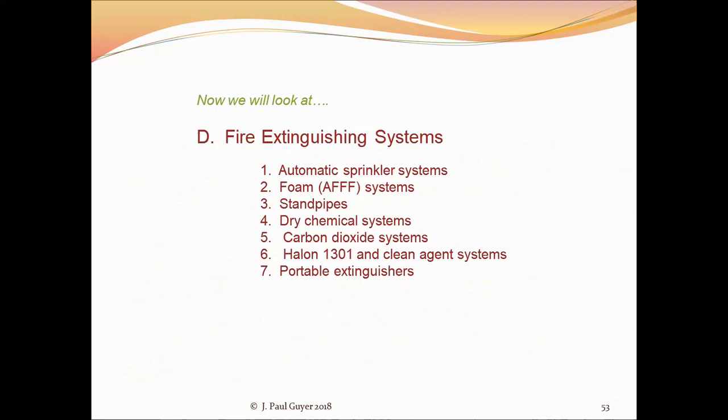The foam systems are similar to a water sprinkler system, except what they do is they mix water with a chemical and then spray that chemical out of these sprinkler heads, and it forms a foam of bubbles that floats on top of the burning fuel fire, like in an aircraft hangar, and it smothers the fire.